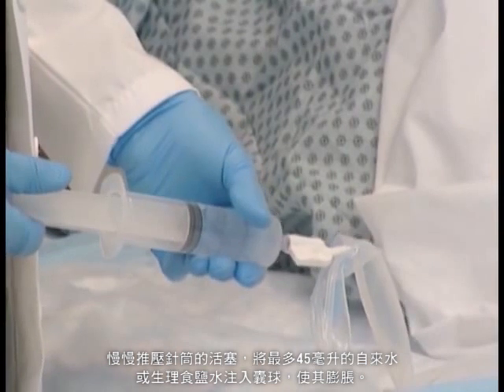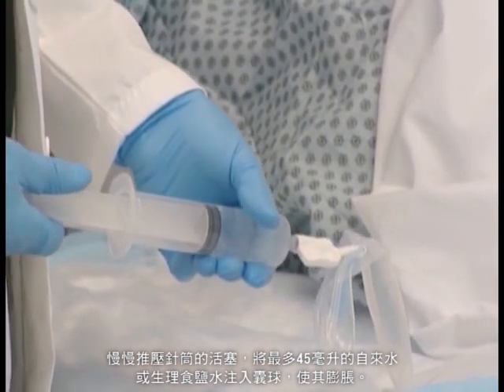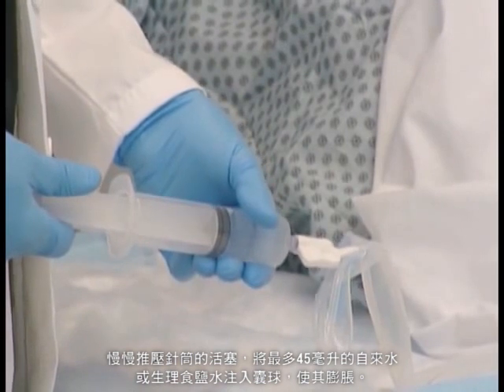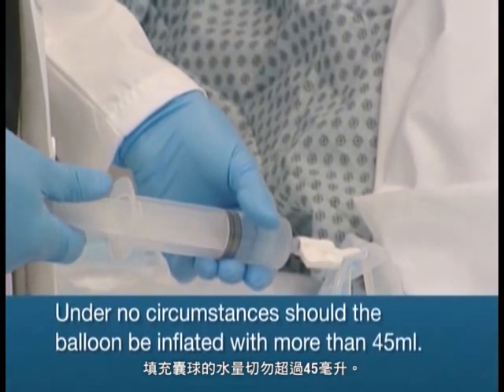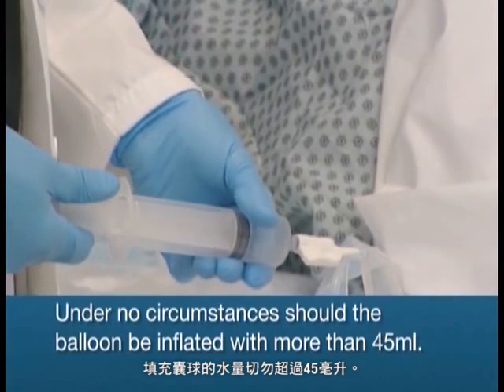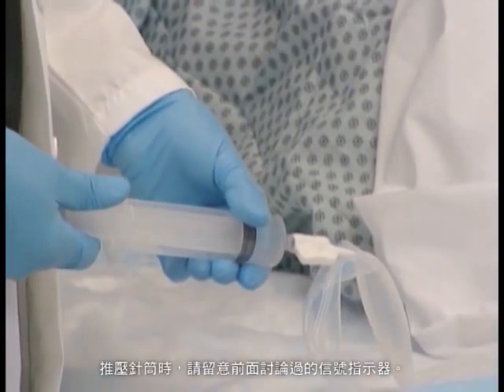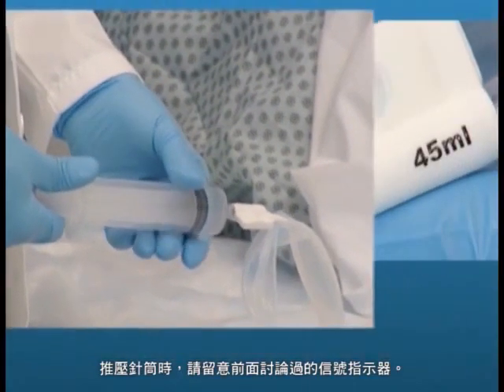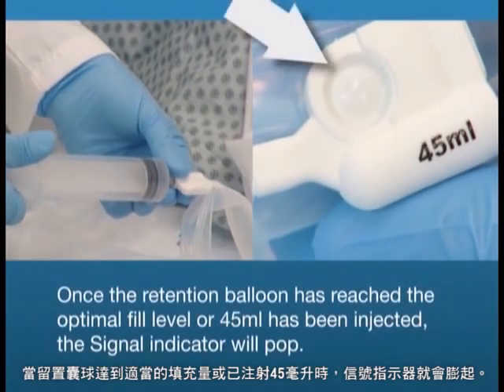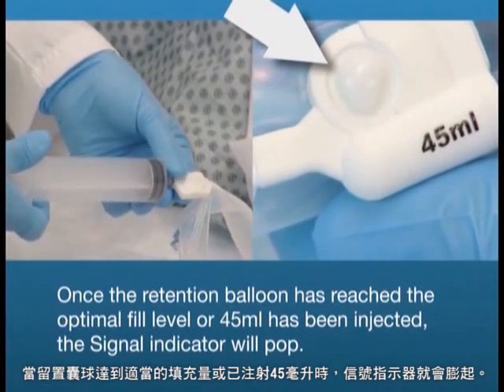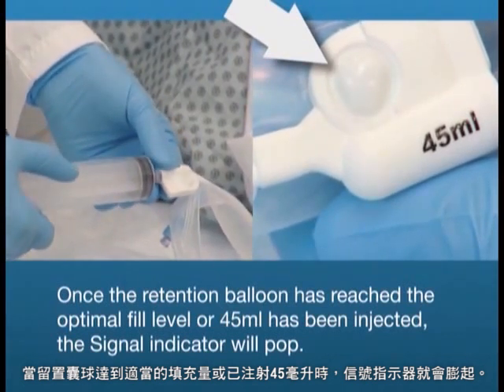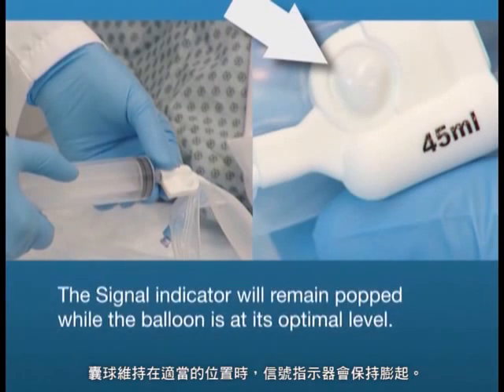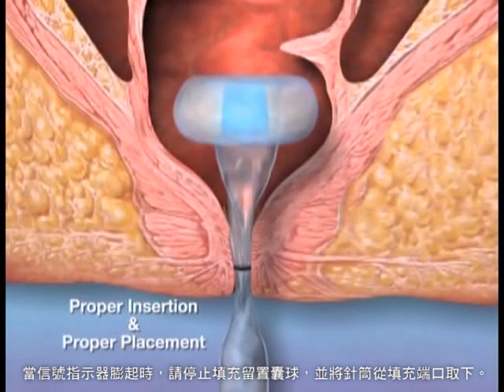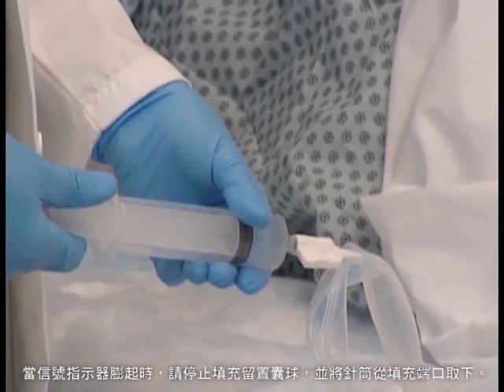Inflate the balloon with up to a maximum of 45 ml of tap water or saline by slowly depressing the syringe plunger. Under no circumstances should the balloon be inflated with more than 45 ml. While depressing the syringe, take note of the signal indicator previously discussed. Once the retention balloon has reached the optimal fill level, or 45 ml has been injected, the signal indicator will pop. The signal indicator will remain popped while the balloon is at its optimal level. Once the signal indicator pops, stop filling the retention balloon and detach the syringe from the inflation port.